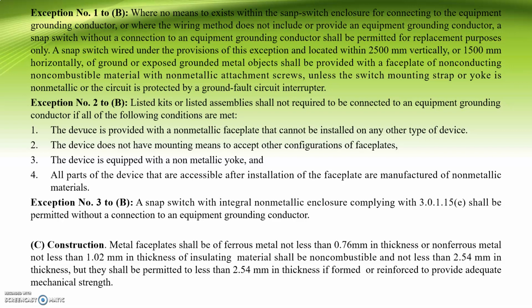Exception number 2 to B. So listed kits or listed assemblies shall not be required to be connected to an equipment grounding conductor if all of the following conditions are met. So the device is provided with a non-metallic faceplate that cannot be installed on any other type of device. Two, the device does not have mounting means to accept other configurations of faceplates. Number 3, the device is equipped with a non-metallic yoke, and last, all parts of the device that are accessible after installation of the faceplates are manufactured of non-metallic materials.